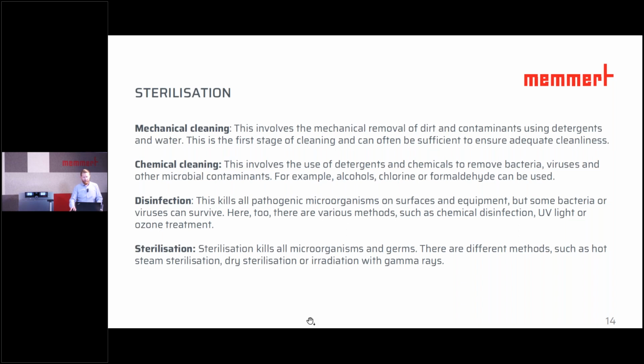Especially in the case of hot air sterilization, which represents the highest level of cleaning, it is important to ensure that this is only carried out at temperatures starting at 160 degrees Celsius and above. Other methods, such as decontamination, never achieve the same level of sterility.